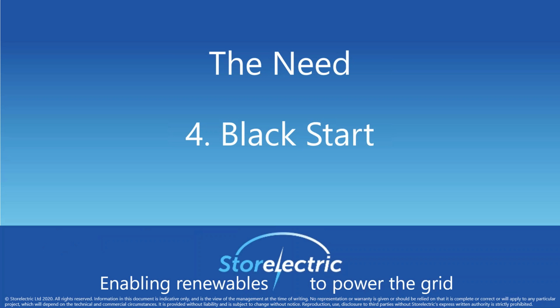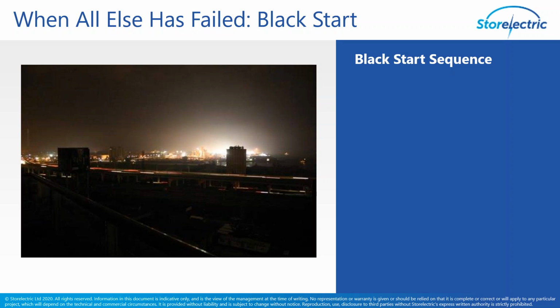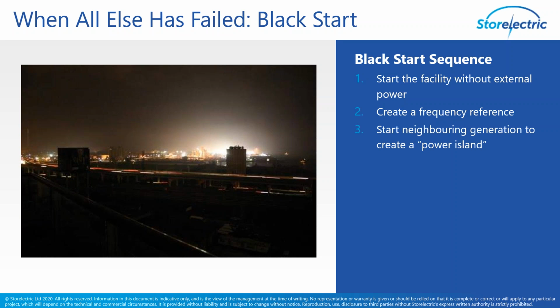Then there are black start issues. What happens when the lights do go out? You need to be able to do a black start, starting a facility without external power. That creates a frequency reference, which enables it, if it's got surplus energy to spare, to start the neighboring generation and create what they call a power island. And you need to deliver all of that. You need power, you need inertia, real inertia, because every time you start up a neighboring plant, it's going to give a hit back onto your own plant. You need to keep the frequency monitored, and you need the duration to be able to keep it up and running long enough to get these other plants started and stabilized. And then the various power islands that are started up are then synchronized with each other.